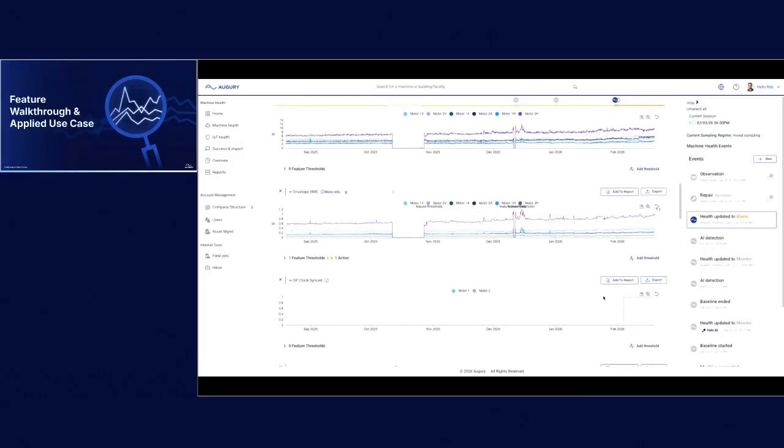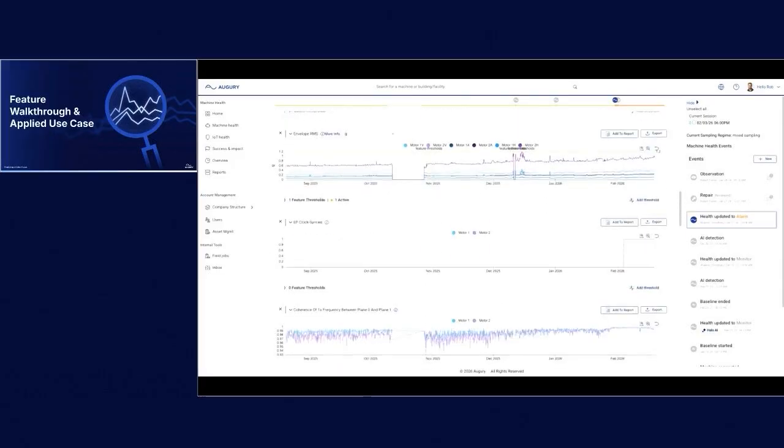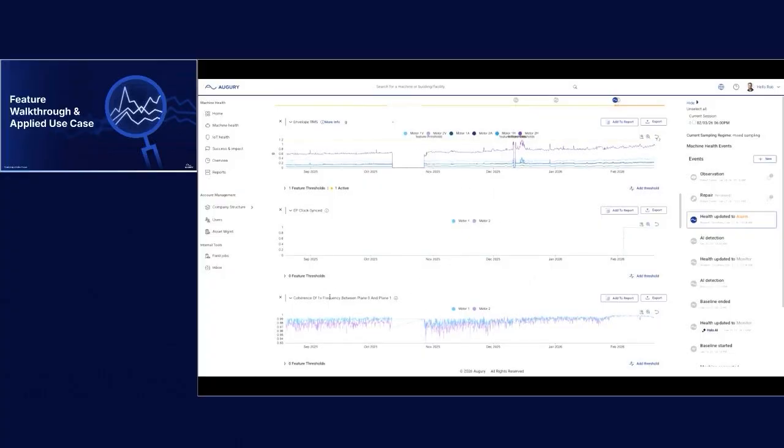Like I mentioned, we have gotten this across the multiple bearings very recently. For this machine, we just opened this up on February 4th. So unfortunately, I don't have the data before this sort of big shift here in the data set, but just wanting to kind of show the feature capabilities here. So the first thing I mentioned, coherence, right? Coherence is very key here. And you can see in this range, like I mentioned, anything above about a 0.8 for us, and really in industry, is considered a good coherence factor.